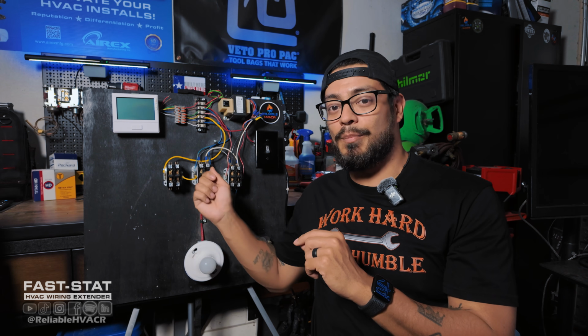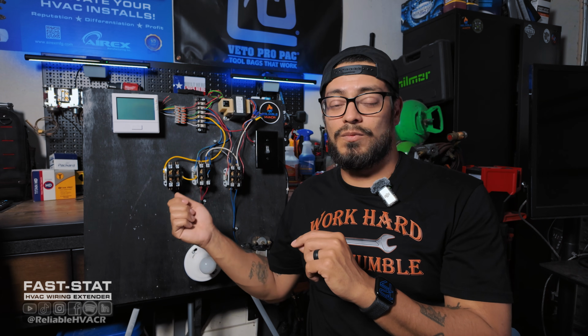All it is, like I said, is a common and a 24 volt wire coming out of there. If those two ever cross paths, you're going to get a short. So if you take your 24 volts and cross it over to the common, you're going to get a short. If that 24 volts touches any bare metal in the housing of the AC unit, whether it's an RTU or an indoor unit, or copper, I've seen that too, where it's laying over the copper pipe outside. That was a common spot that I've seen, because copper is conductive. That is actually what your wiring is made out of, copper strands or a solid copper piece.